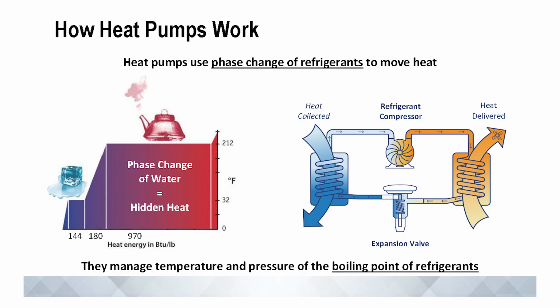All it has to do is get the refrigerant colder than outside. That's the number one thing. If the refrigerant is colder than outside, it can absorb heat from the outside air. Doesn't matter that it's -20, because this stuff boils at -50, right? So it absorbs heat as phase change, goes from liquid to vapor on the outside.